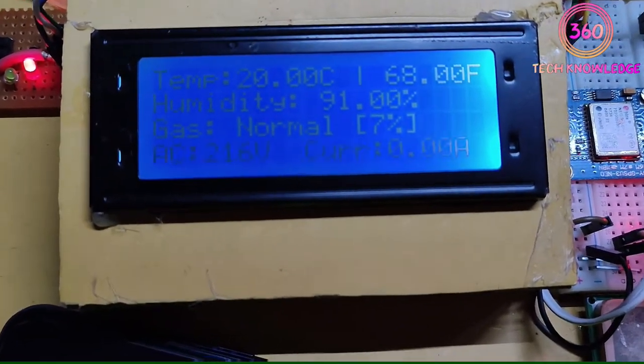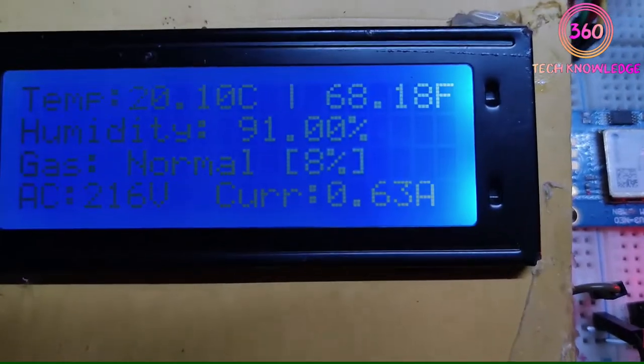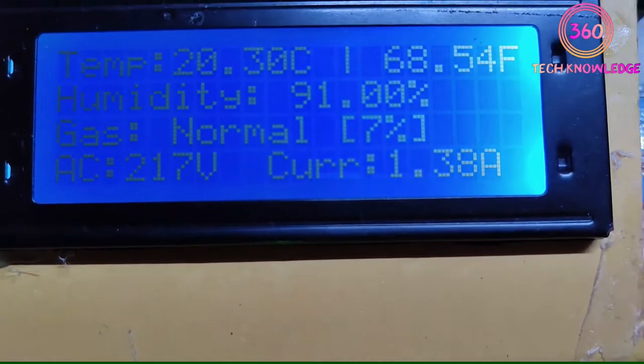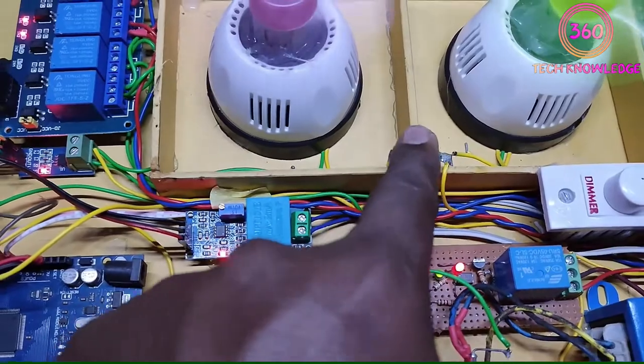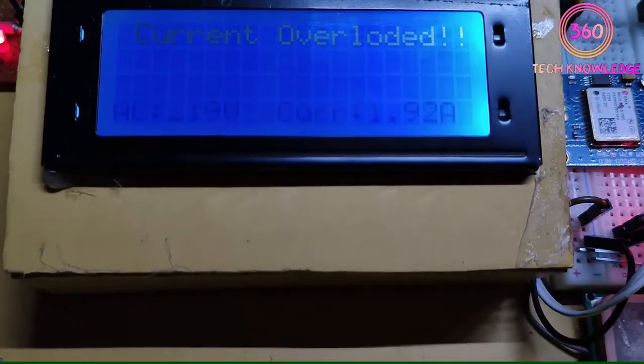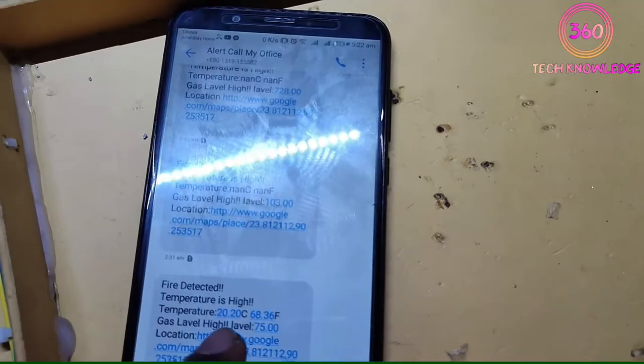Let's check the current overload issue. We can see on the display that our current is 0.00 Amp because we have no load. First, turning on a fan to see the load — we can see a current of 0.63 Amp. Now powering two fans together — we see 1.4 Amp current consuming, which is normal load. Our main power transformer is 1.4 Amp. Now I make a short circuit for overload — we can see on the display that the current is overloaded, the alarm is ringing, and the main power is off. Instant calls and SMS have arrived on our mobiles.